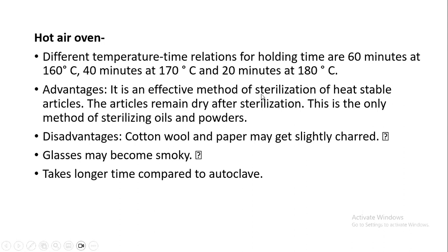Advantages: it is an effective method of sterilization of heat stable articles such as glasswares, or sterilizing of oils and powders can be done by making use of hot air oven. Disadvantage is cotton wool or paper may slightly get charred, and sometimes you will have a smoky smell on the glasswares. And one of the disadvantages also, it takes longer time compared to autoclaving.